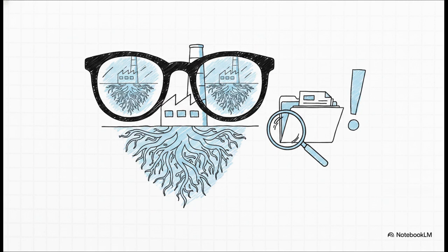Now, what's really interesting is to look at this from an inspector's point of view. When they walk through your doors, what exactly are they hunting for? Well, they want to gauge the true maturity of your analytical program. They're going to immediately look for comprehensive ICH Q2(R2) coverage. They will directly probe your LOD and LOQ against your acceptance criteria. They want to know if your method can actually detect the limit in the real world. They're looking for realistic specificity testing, rock-solid system suitability, and totally rigorous investigations anytime there's an out-of-specification result. Ultimately, the depth of your validation is what signals your operational discipline to them.